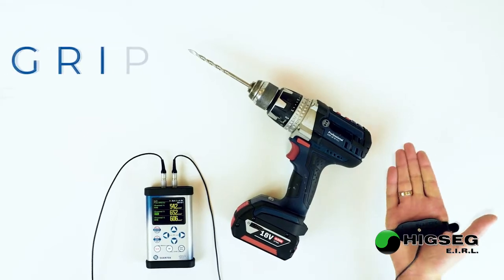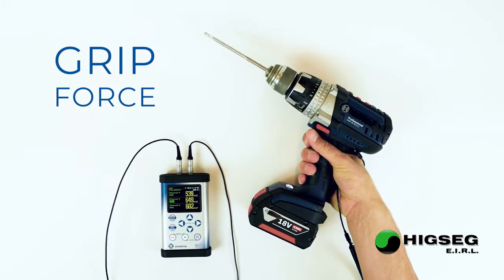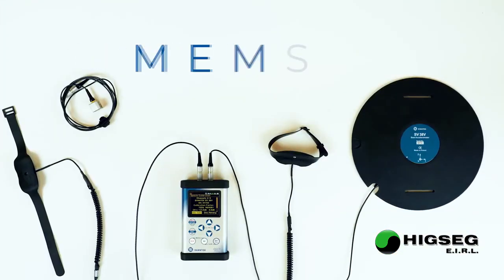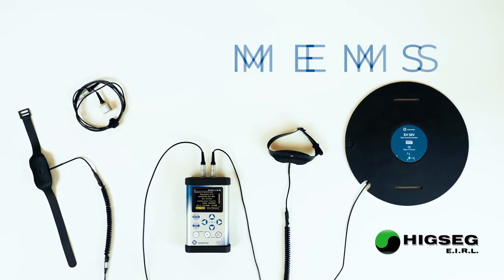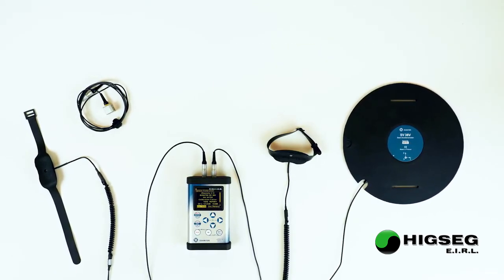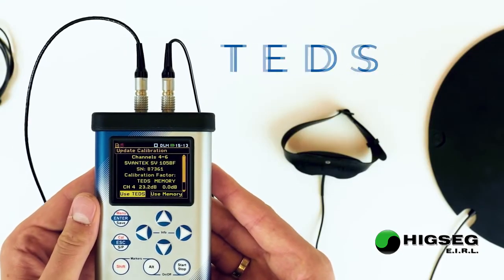Evaluation of the grip force is possible with the dedicated integrated adapter SV105BF. Svantek sensors use MEMS technology, which is more robust and less power consuming than standard piezoelectric accelerometers. Each sensor is equipped with TEDS memory with the calibration factor.